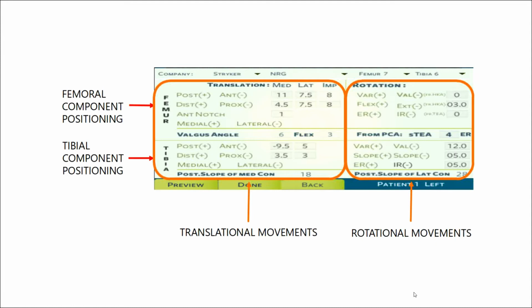The fourth row allows for medial and lateral translation of the implant with similar sign buttons. As it will have no effect on the size of the cuts, no number boxes are there in that row.